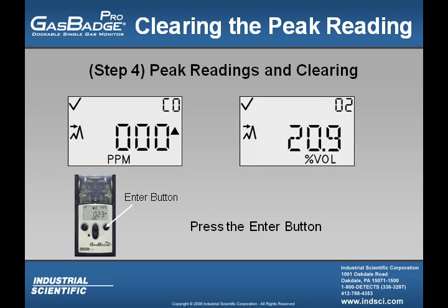If the user is trying to clear the sensor peaks, they will have to press the Enter button. Once the user presses the Enter button, if the user has a toxic sensor installed, the reading will go back to all zeros, just like the screen on the left. And if the user has an oxygen sensor installed, the reading will show 20.9, which is the percentage by volume in a fresh air environment, just like the screen on the right.